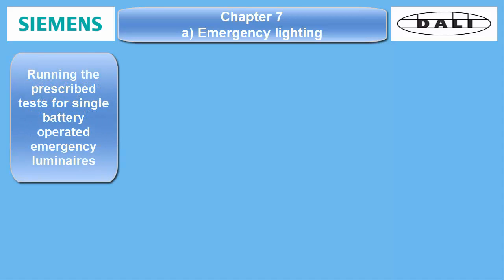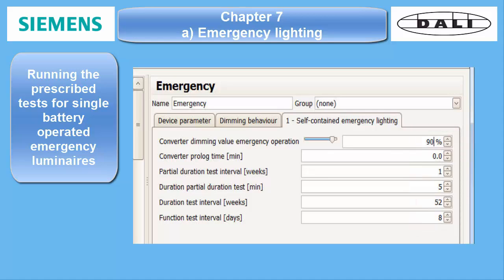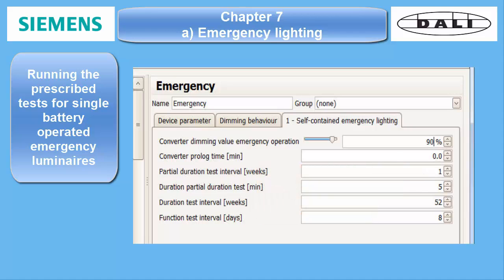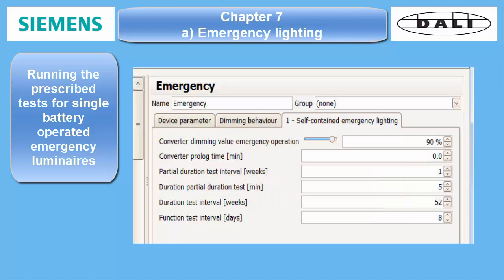3. Running the prescribed recurrent checks. The settings for the checks must be made individually for each ballast of type 1. As such ballasts also have an internal counter which will be set by the DALI gateway, they will start the timers for the checks right after download. The automatic check runs will be carried out according to the parameter settings and run randomly on the calculated days — especially the endurance tests, not all at the same time, as this can cause severe problems in case of a real emergency.